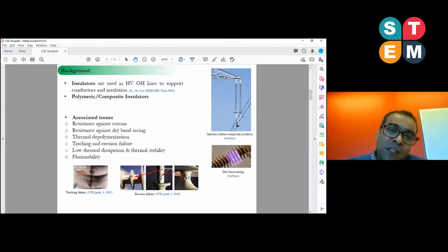In the presence of some moisture, or even sometimes light rain, that can initiate electrical dry band arcing due to high leakage current on the surface of the insulators. That high leakage current can easily increase the surface temperature, and that temperature can thermally depolymerize the polymeric surface. Sometimes we can even see some flammability on the surface of the insulator. That carbon path is called electrical tracking, and that one is called erosion on the insulator.